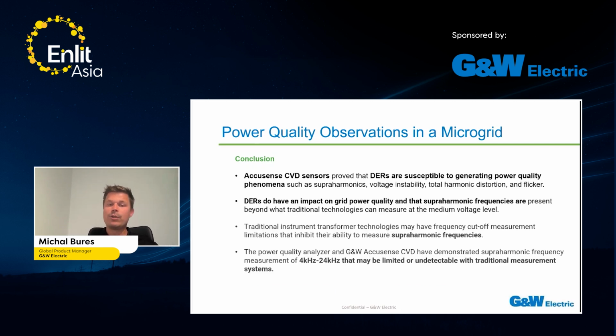So what is the conclusion of this real test? The Accusense sensors helped us prove that the DERs are the ones causing the power quality issues, all the phenomena that we just listed: supraharmonics, voltage instability, harmonic distortion, and flicker. Also, the DERs have an impact on grid power quality, and they are probably the main cause of the supraharmonic frequencies. The point is that it is there. We just need to understand, we just need to measure and do some correction.